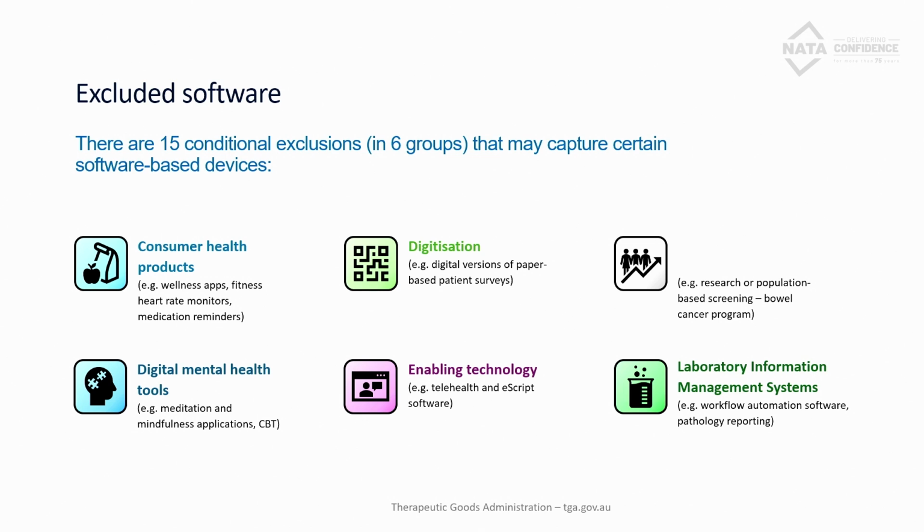And what we're seeing is that while we had LIMS that might have been introduced at the beginning of the IVD regulatory framework, and they may have met those exclusion criteria in 2021, there's a lot of additional functionality that software developers actually put into their products. They roll them out. Often the users are not even aware of it. It's just a version change or an upgrade. And it's really important because a lot of the time those products are actually being pulled back into a regulatory product. They're making decisions about and changing the results and the outputs of those pathology results. So they are a regulated product, and we know that there is a compliance issue in this space.